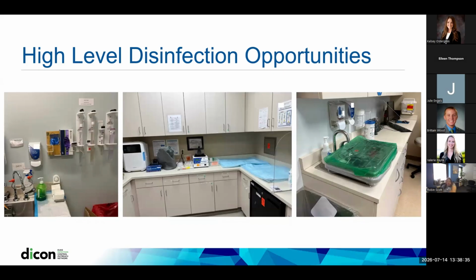There was no clear evidence that they were timing the duration the scopes were being put in that solution, and MEC checks were lacking. And then finally, from a reprocessing space standpoint, they also had these biohazard bins directly underneath those solution canisters or cylinders. Everything was very tight and not in a great dirty to clean flow. We also couldn't find good evidence of how the scopes were rinsed when they were removed from that solution. So for all of those reasons, we said, wow, we have to really put a pin in this, move to disposable scopes for a while, and then readdress.